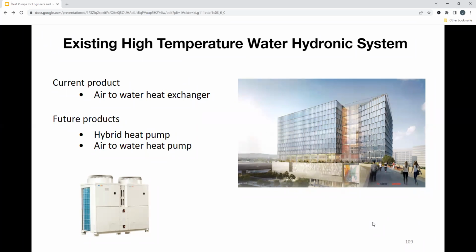Right now, one of the options we do have, if you are working with water fan coil units, is using a heat pump, right? An air source heat pump connected to a water heat exchanger, right? So you have refrigerant going to the water heat exchanger, and these are low temp hot water, so we can get up to 113 here. You can see this used for radiant floors. You can also use this to maintain your condenser water loops, right? Keeping around 90 degrees or whatever your design conditions are. You are able to use these air to water or refrigerant to water heat pumps to maintain that loop. So that is the option right now.